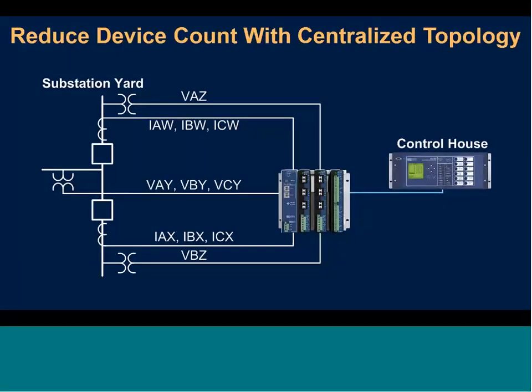And the flip side of that is here's a topology that reduces the device count. In this case, we have the same analog signals, so we still have all the same number, but this time we're running them all to a single Axion node. So we have to have a couple of CT-PT cards, which we're showing here, but the nice thing is I only have to buy one Axion, with the understanding that I now have to run copper connections to that single Axion.